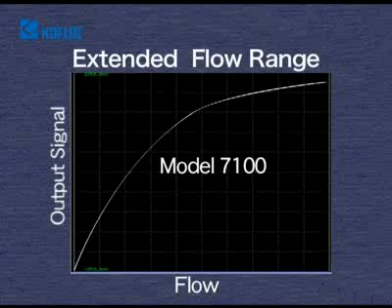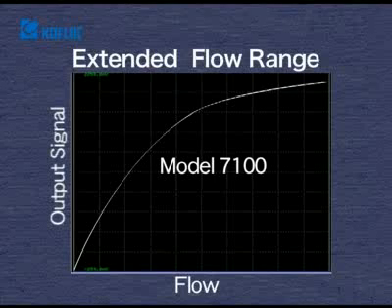Thanks to the resulting absence of the reversing phenomena, even if the flow rate increases beyond the specified range, there is no fear of misjudging the flow rate.